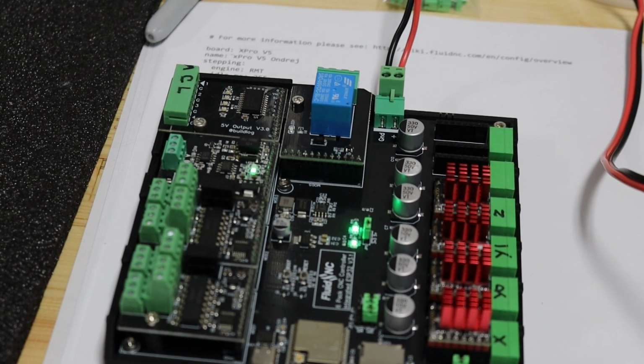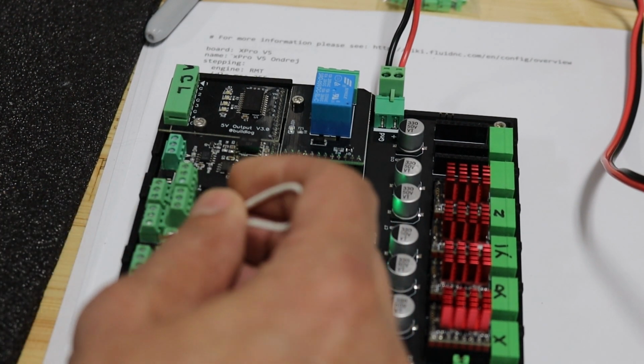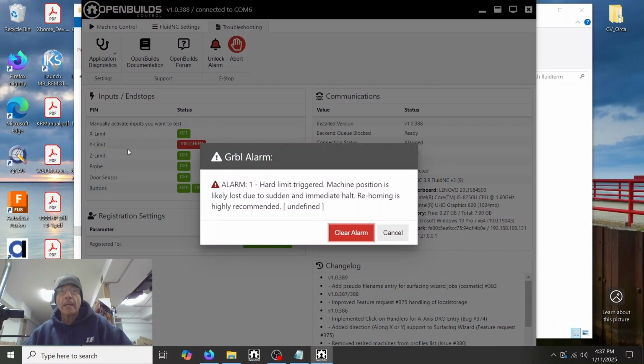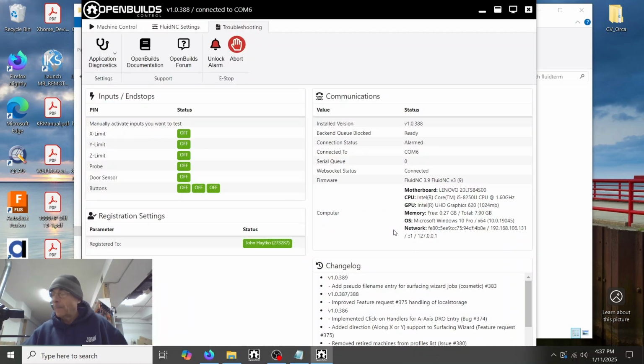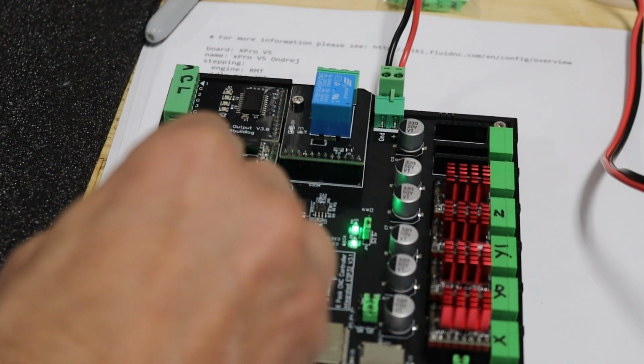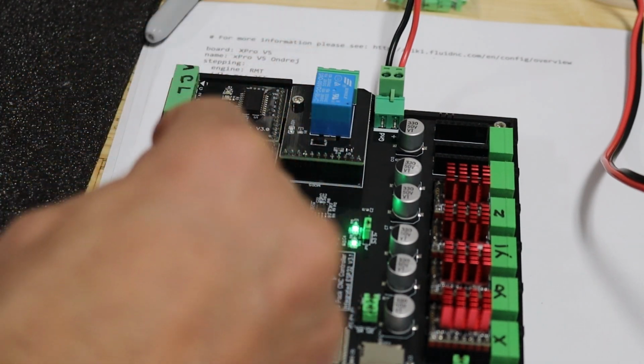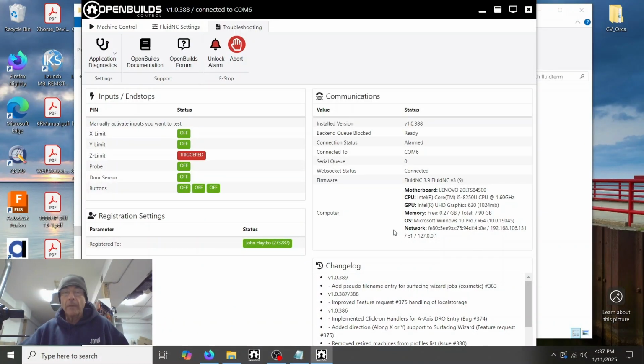Okay, so we are going to hit the Y limit switch, and as you can see, it triggers an alarm, and the Y limit switch is hit. Now we'll do the X, and we'll do the other Y, which it can't differentiate between, but at least you know it works. Here's the Z limit switch, and those are all tested.